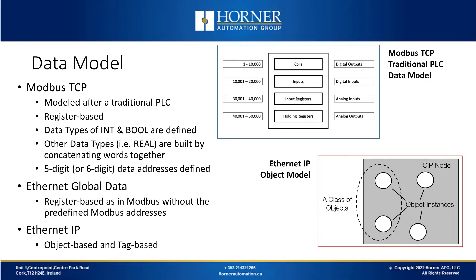Modbus also includes an addressing scheme that traditionally is a five-digit address consisting of four different types of data: coils, inputs, input registers, and holding registers. Ethernet Global Data was also created in the era of register-based PLCs, in the 1990s by GE, so like Modbus it's based upon boolean and word-type variables, but has been later adapted to include 32-bit data types. Unlike Modbus, Ethernet Global Data doesn't have the specific predefined Modbus addresses. Ethernet IP was adapted in the early 2000s and it's an object-based and tag-based model, as opposed to register-based.